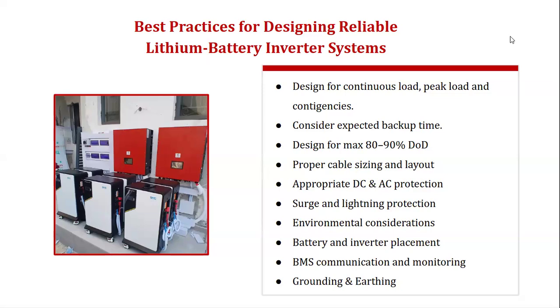So it's important to size properly and lay them out well to make it neat. This will eliminate temperature rising and shutting down when the battery is not actually low but the inverter senses it as low, overworking and stressing the BMS - because all the cables must be proper standard.